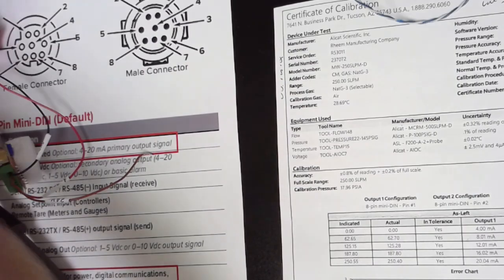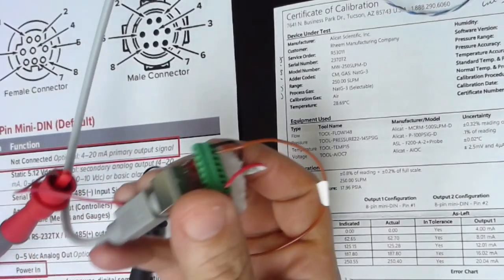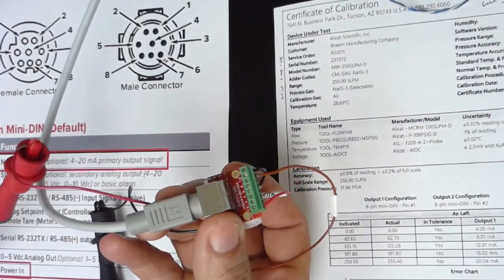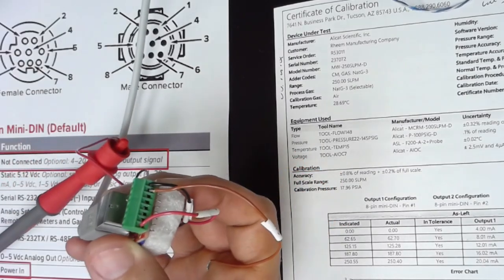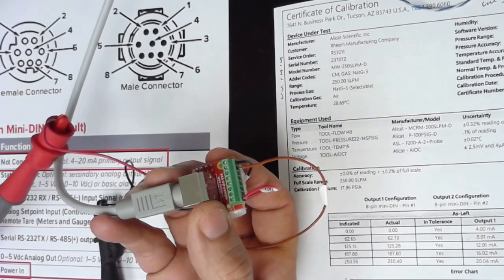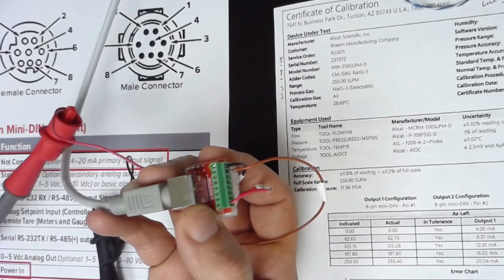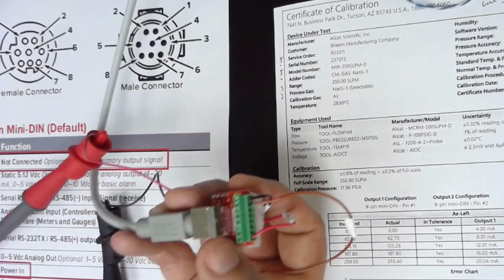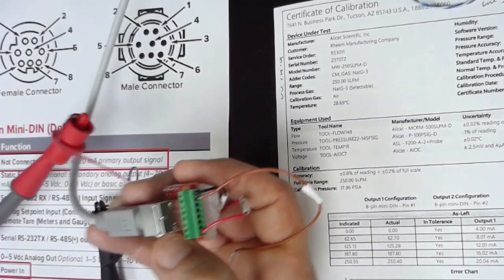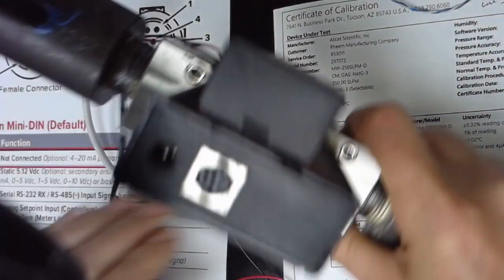We've got some different features here than most of our other calibrations. First of all, we use an old 8-pin mini-DIN serial cable. I've bought these adapters and put one in each process meter box that we have in the facility. You're going to be calibrating from the point where the cable plugs into the Alicat because we have to take into account the resistance of the wire. Some of these cables are over a hundred feet long.